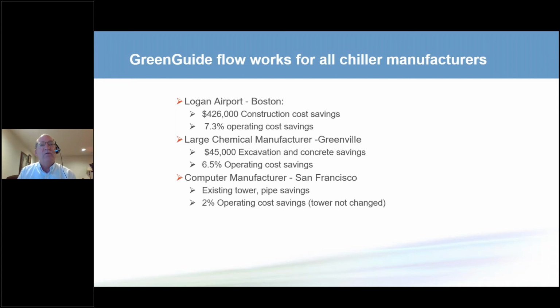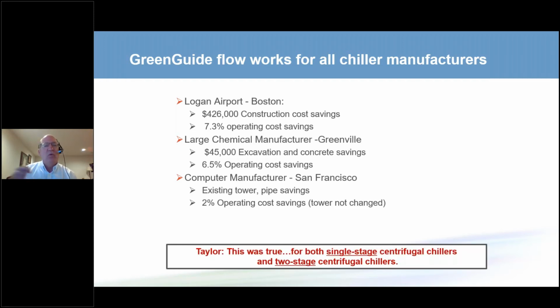There was a computer provider based in San Francisco, and they had a study done for them by the local utility. They used the existing pipes, or an existing tower, they reduced their pipe size, but their installed costs and their operating costs went down. These jobs were done by 3 different chiller providers. And as Mr. Taylor said, there is no difference. It works for single stage and 2-stage chillers. It doesn't matter who is providing the chiller.